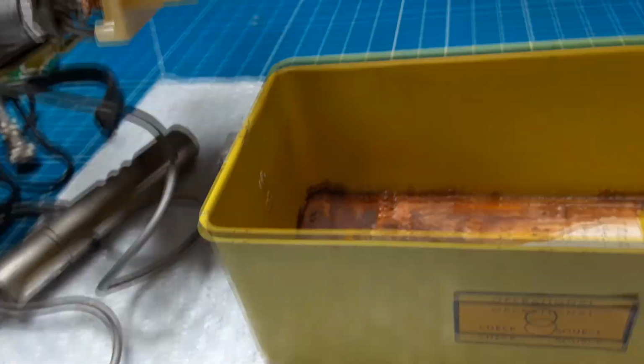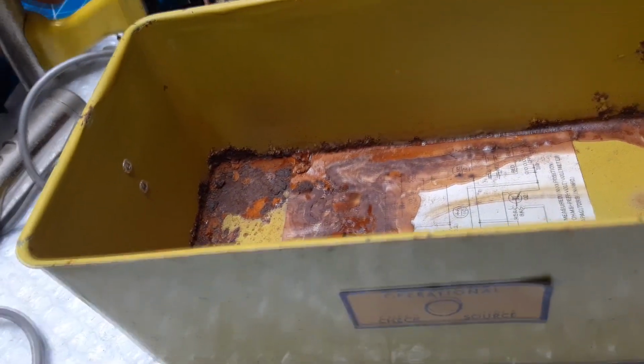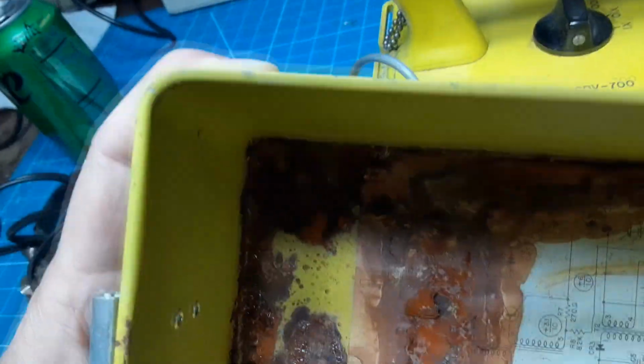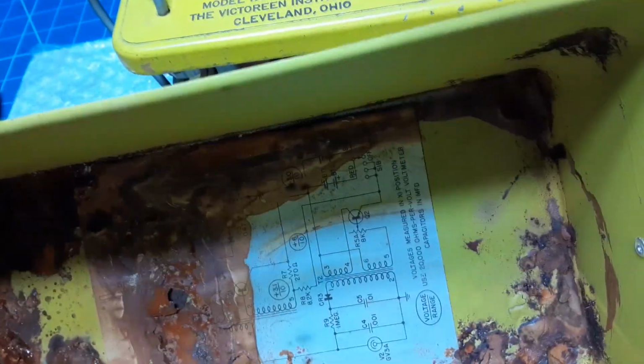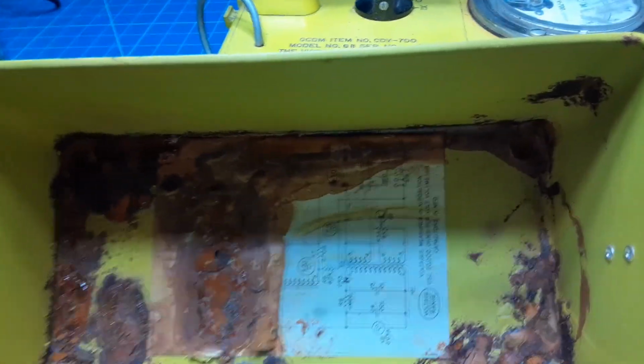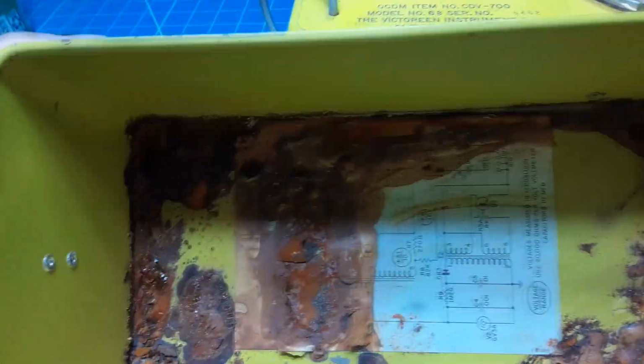Okay, this is the unit and this is the case. Let me set the unit down and we'll take a look at the case first. You can probably see there was a schematic diagram in there. There's a piece left. But the case is full of corroded, rusted metal, and that's where the corrosion from the battery case came. I'll try to get all that out of there so it doesn't do more damage to the inside of this case, and perhaps hit it with a yellow primer and stick a new schematic diagram down there if I'm able to do that, so that it'll be back to its original information.